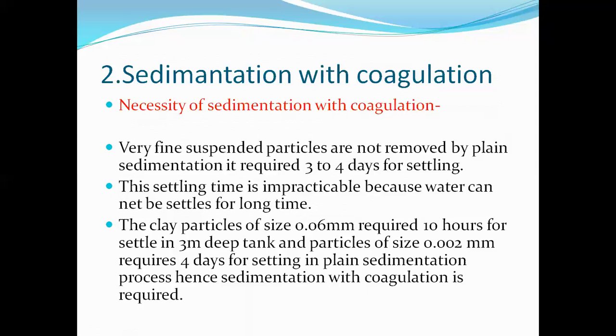The third necessity is that clay particles of size 0.06 mm require 10 hours to settle in a 3-metre deep tank, and particles of size 0.002 mm require 4 days for settling. This time period is very long. Hence sedimentation with coagulation is required for the settlement of these particles.